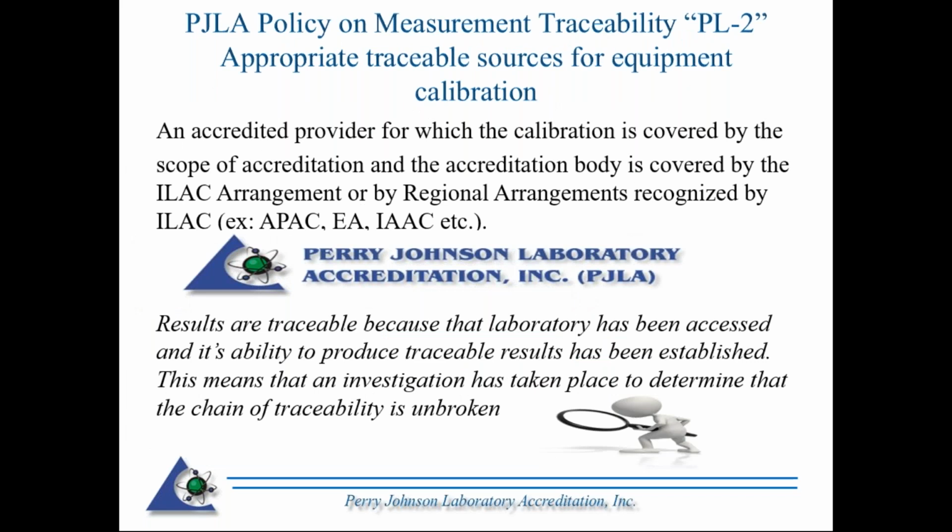Also, as far as traceability sources, you can go directly to an accredited provider for the calibration, just to be assured that it's covered under the scope of accreditation. And they are accredited through an entity that is recognized under the ILAC arrangements, regional arrangements recognized by ILAC, which we are an MRA signatory here at Perry Johnson. There are a few others here in the U.S.